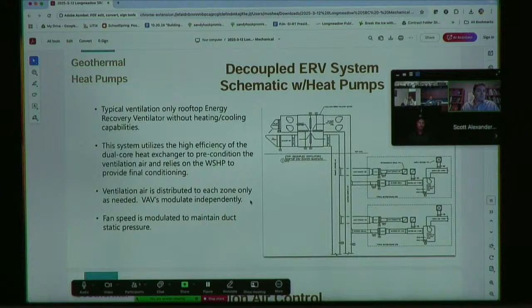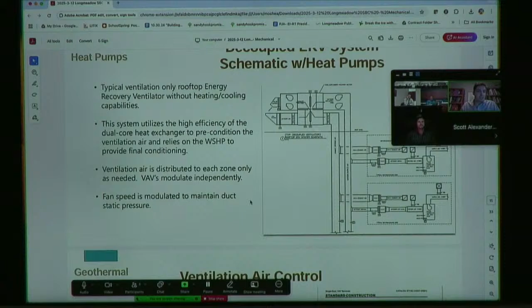So each individual space that has occupants, like a classroom, for instance, will have a CO2 monitor, and that will control how much ventilation air is being provided there. So as CO2 levels rise, the VAV box opens and moves more ventilation air to maintain the CO2 levels in the space. The fans within the energy recovery units will then modulate up or down as necessary to maintain static pressure within the ductwork, and that's how they react to the demand.